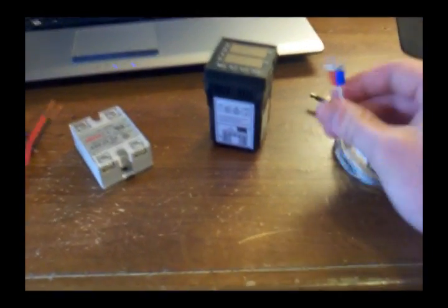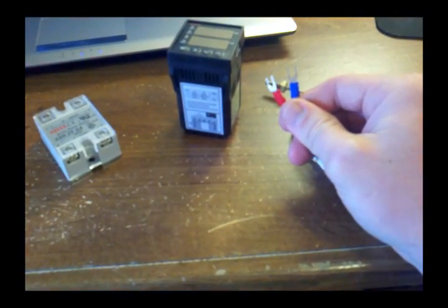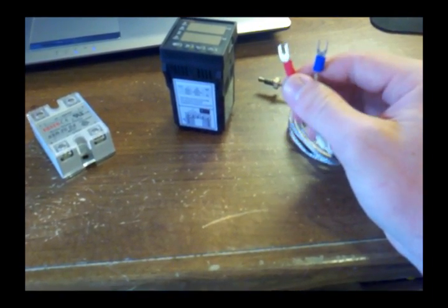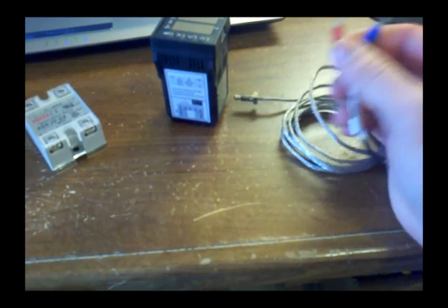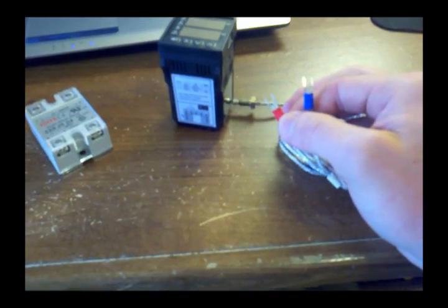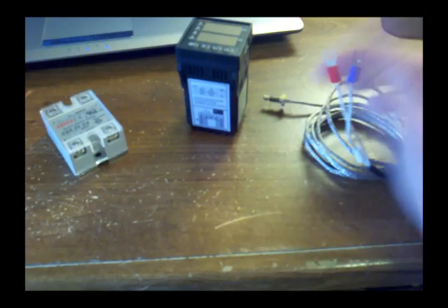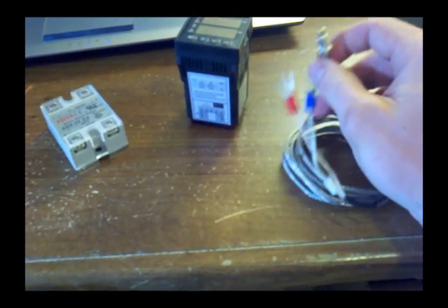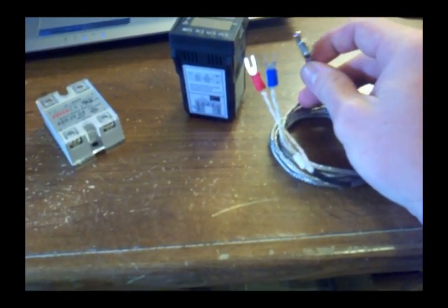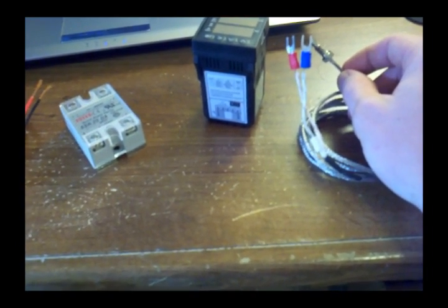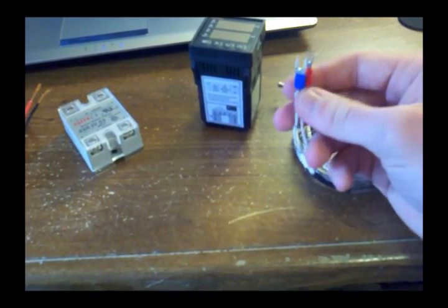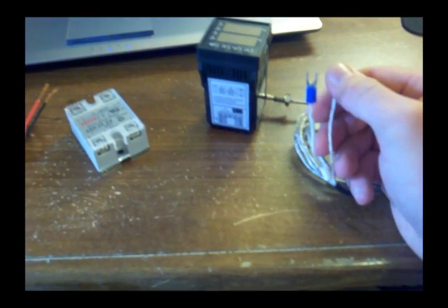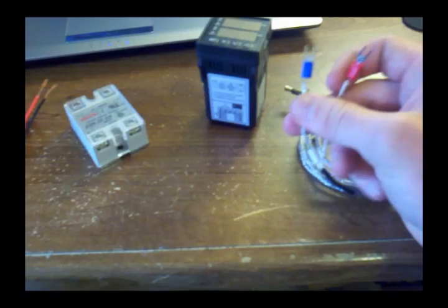Like, for instance, which one of these is positive and which one's negative? I found a website that said the industry standard for thermocouples was that the red was negative. So I wired it up that way, and when I put the end of the thermocouple in my refrigerator, instead of the temperature reading going down, the temperature reading was going up. So I tried it the other way, and I put the blue on the negative terminal and the red on the positive terminal, and then it was going in the right direction.